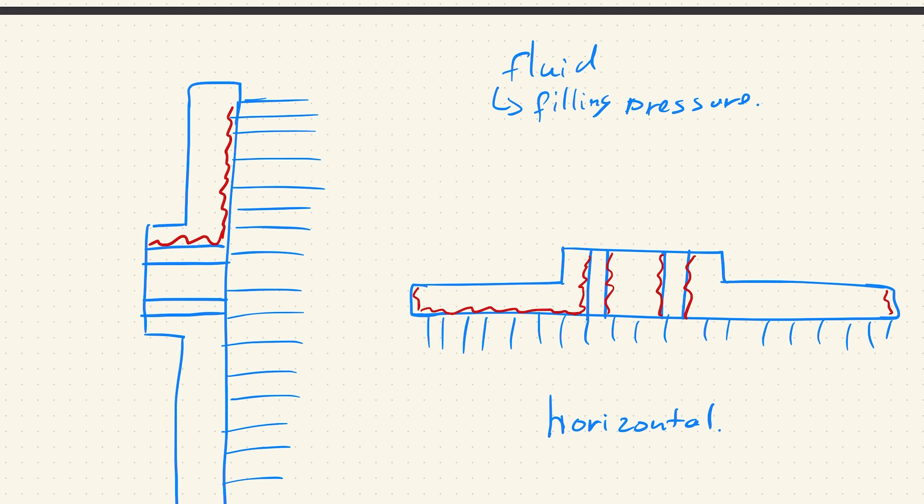What also happens is that when you have actual heat flow happening inside of the heat pipe it will also change pressure. So generally if you have a higher pressure then you would have a higher temperature. If you have lower pressure you would also have lower temperature if it works correctly. The thing is that this happens both ways around. So if your temperature goes too high then the heat pipe will kind of cook itself and you get less performance out of the heat pipe. If you choose your heat pipe to work at a higher temperature then the ratio between the vapor and the fluid is not correct and that would also give it less effectiveness on the heat pipe. So generally what you want to do is at the temperature range that you wanted to work at most effectively, that's where you set the charging pressure at.